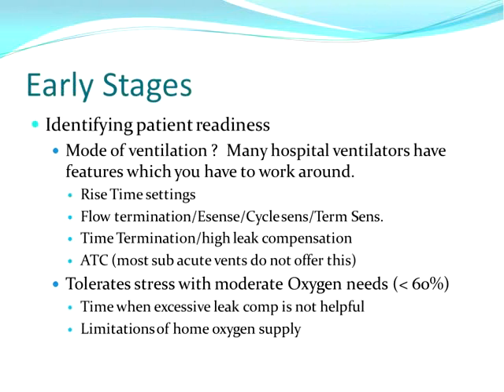Unfortunately, in the critical care environment, unlike anesthesia, all of our ventilators are labeled differently. This is a project that's kind of been started and stopped throughout the years to try to standardize nomenclature on our critical care or respiratory therapy ventilators. We still haven't gotten to that point, so sometimes there are challenges with recognizing the labeling or terminology that's different on our ventilators one to another. So for example, rise time. Most ventilators call rise time how fast the air is going to come in a pressure mode, either pressure control or pressure support. They may vary in the way that they do it or the way that it's labeled.